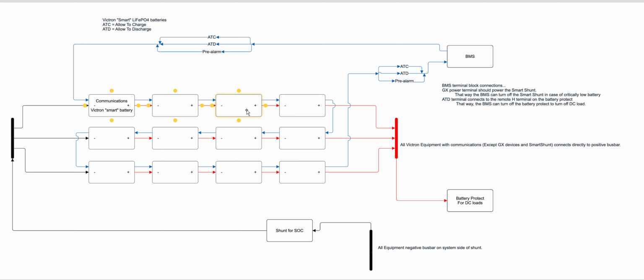If any one of the batteries throws a pre-alarm where it's saying, hey, there's an imminent shutdown coming, then it will disconnect the pre-alarm, and the BMS will see that there's no continuity from pre-alarm to pre-alarm, and so then it'll throw a pre-alarm alert. So it's just a dead simple communication scheme.